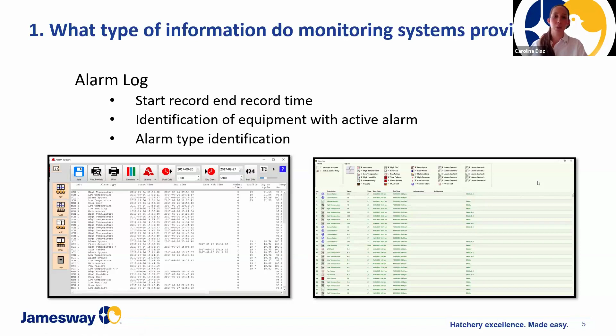An extra bonus is that if you have users set up, you may be able to see who did or didn't attend to that alarm, if you have a maintenance team. That's very important, especially for troubleshooting, because one of the first things I want to check is what type of alarms the machine had during the incubation or hatchery cycle. It gives us clues about what was happening with the machine, or if something was wrong.